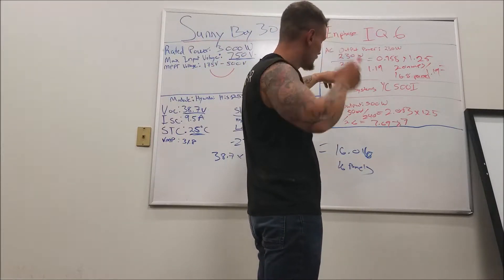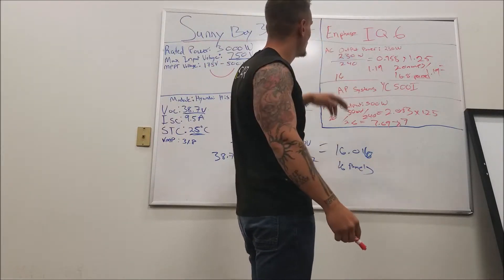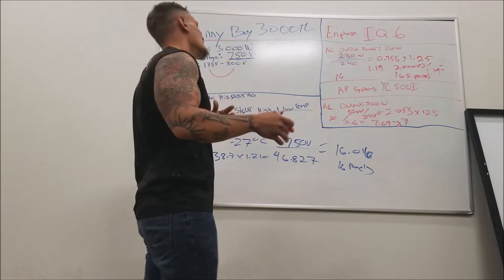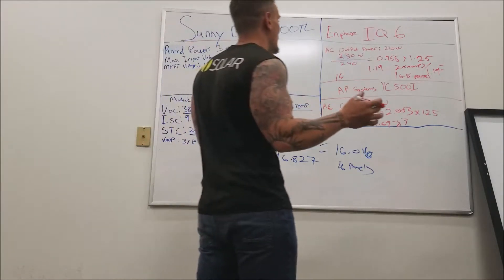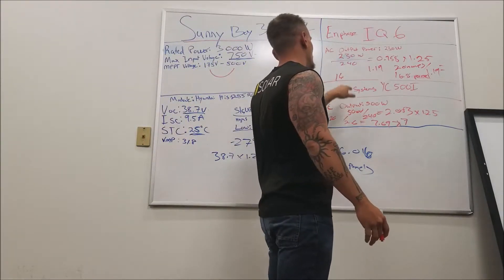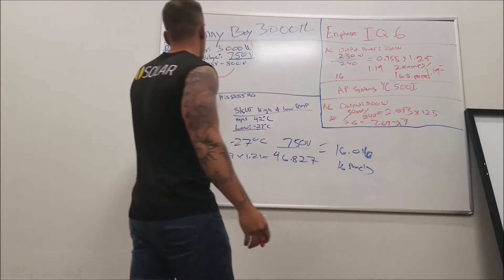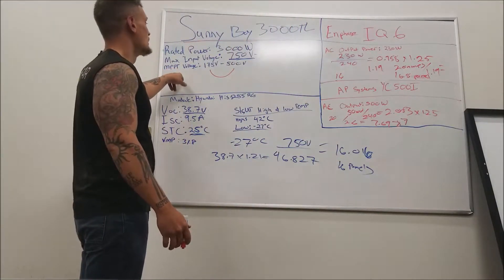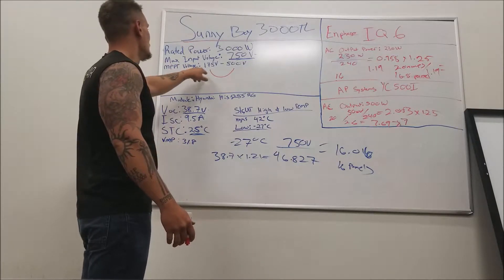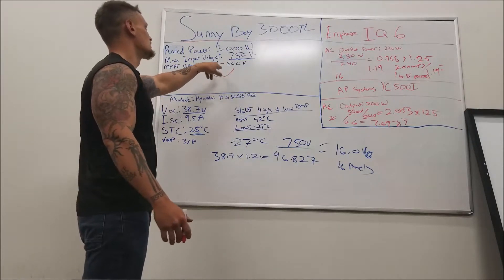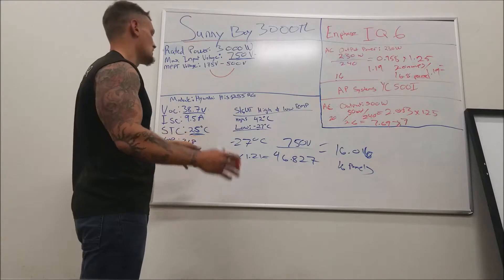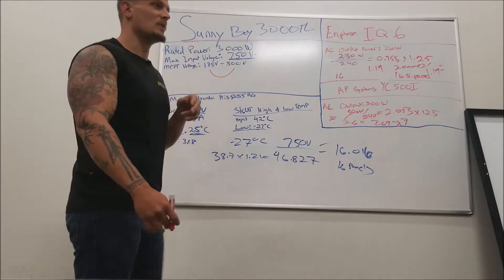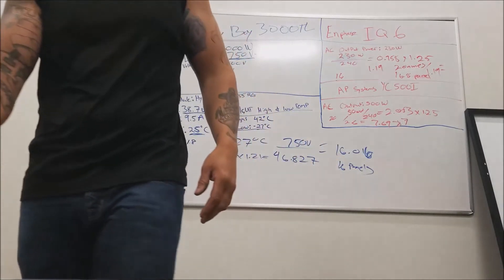With the two microinverter types we're looking at, the maximum power point tracking happens at the panel level, so it's not going to change with how many panels you have on a branch circuit. With the Sunny Boy string inverter, the maximum power point tracking is at the string level, so that is going to change — your voltage is going to change, affecting how many panels you can put on and stay in range.